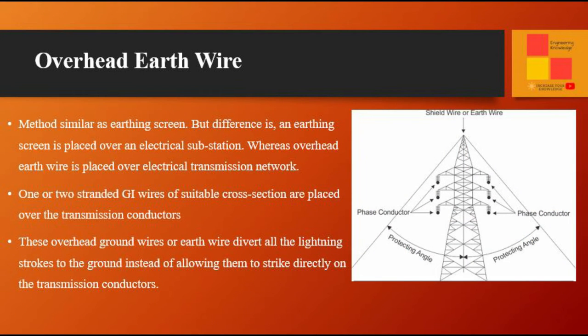Overhead earth wire is a method similar to earthing screen, but with a difference: an earthing screen is placed over an electrical substation, whereas overhead earth wire is placed over an electrical transmission network. One or two stranded GI wires of suitable cross-section are placed over the transmission conductors. These overhead ground wires divert all the lightning strokes to the ground instead of allowing them to strike directly on the transmission conductors.